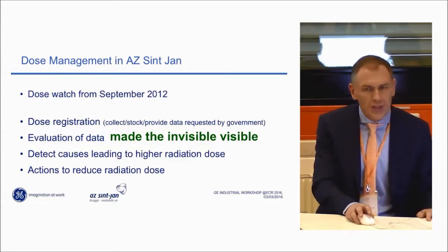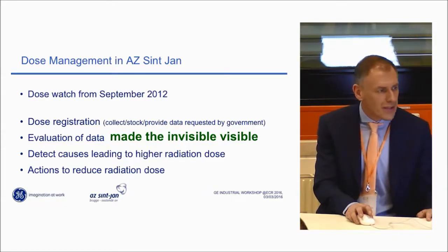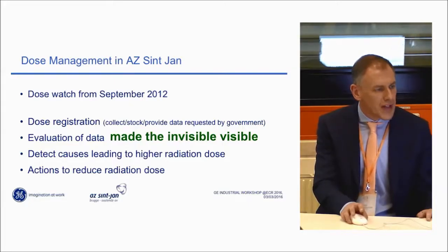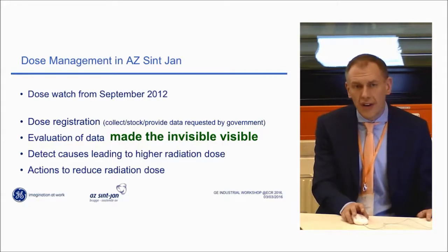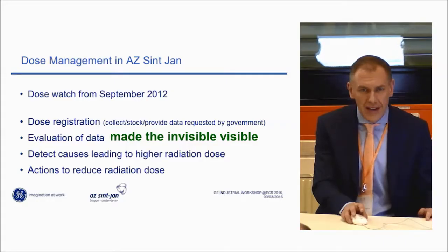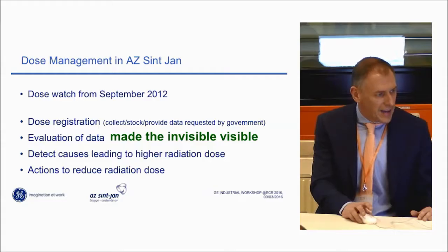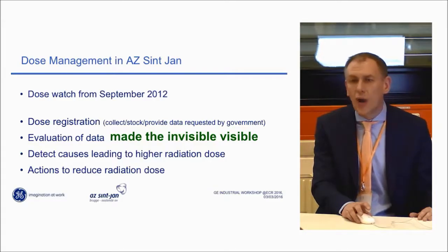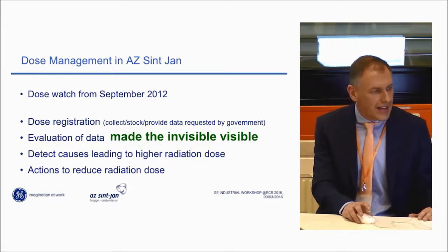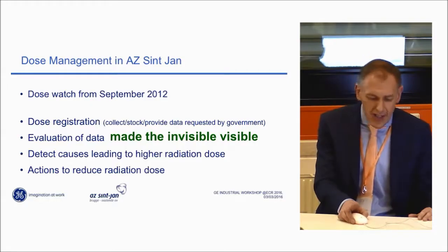We started using DoseWatch in Bruges from September 2012, not only for dose registration but also for evaluation of our data. DoseWatch made our doses visible — it made the invisible visible — and by doing so we could detect some causes leading to higher radiation dose, and then actions were undertaken to reduce radiation dose.